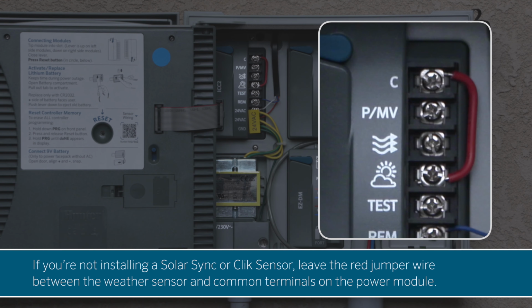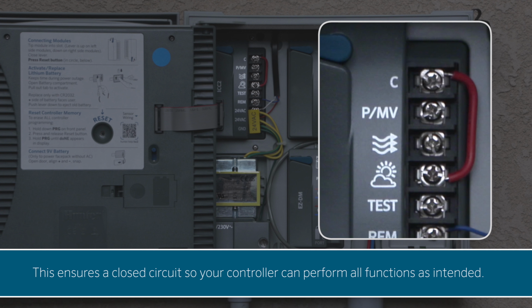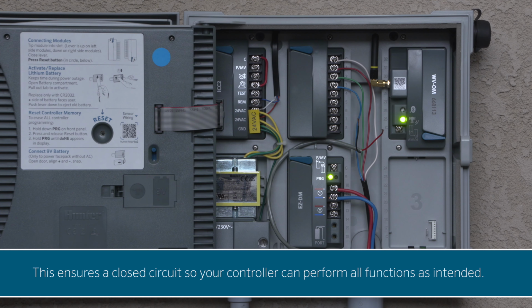If you're not installing a Solar Sync or Clik sensor, leave the red jumper wire between the weather sensor and common terminals on the power module. This ensures a closed circuit so your controller can perform all functions as intended.